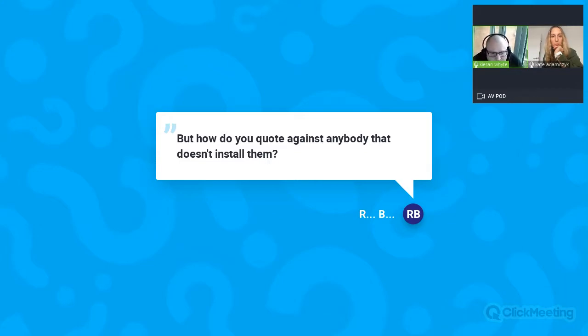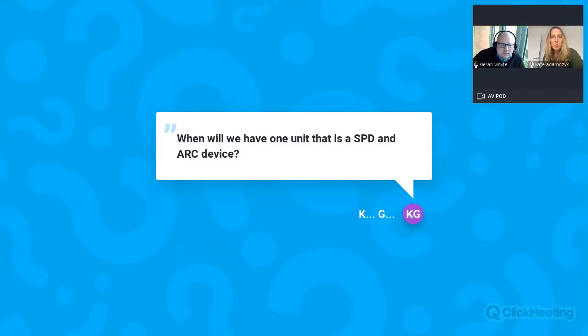So there's a question there about when will there be a combined SPD and ARC. I'm assuming you're talking about an arc fault detection device combined with a surge protection device. Well, the regulations for AFDDs don't allow you to have it as head of circuit. If you imagine a split load board where you'd have the RCD, you're not allowed to have an AFDD like that. It would have to be for individual circuits. So the current situation of having an SPD protecting a single board should be adequate.